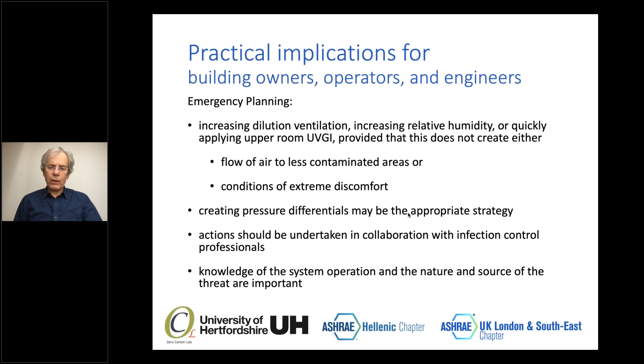Now, emergency planning also needs to work on increasing dilution ventilation, increasing relative humidity, or quickly applying upper room UVGI disinfection, ultraviolet germicidal irradiation. And this needs to be done provided that it doesn't create either flow of air to less contaminated areas or conditions of extreme discomfort. Creating pressure differentials may be the appropriate strategy, as we have seen from a few slides ago. And these actions should always be undertaken in collaboration with infection control professionals. But knowledge of the system operation and the nature of the source of the threat are very important.